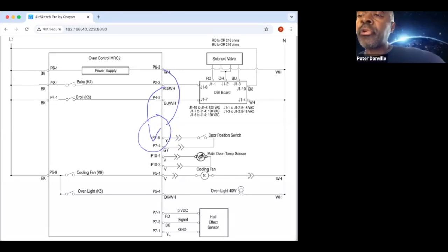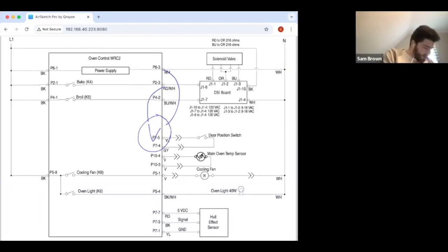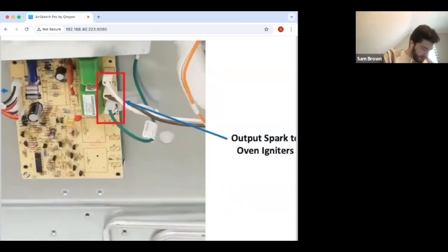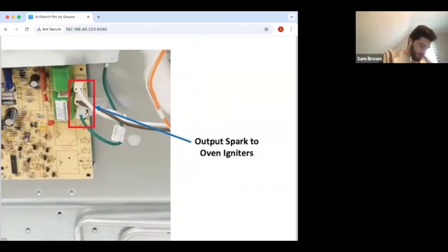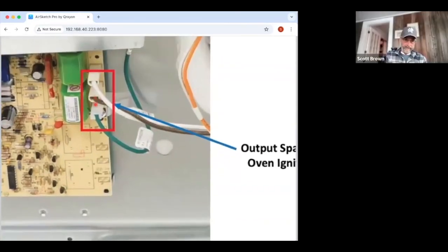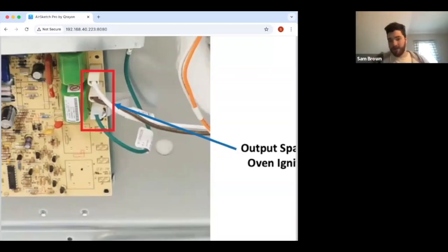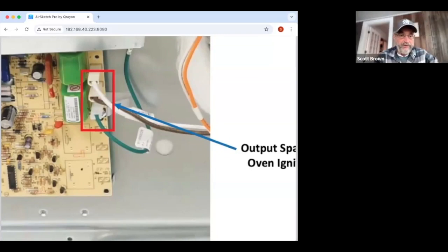Quick question. Could you go over again where you do not test? You talked about high voltage. Just want to clarify, what do you not want to test? Yeah, they don't show it here on the schematic, but it's these wires coming off of here. Those are the spark output to the igniters. That's your high voltage. You don't want to put your meter probes in there. 12 to 15,000 volts, far outside the range of your meter. You could put one probe in either the white or brown wire, put your other probe in the green wire, fire up the spark, and your meter will blow up. Wow. So don't do that.